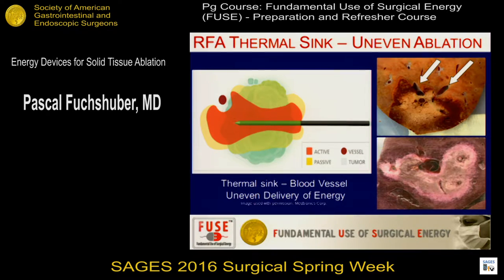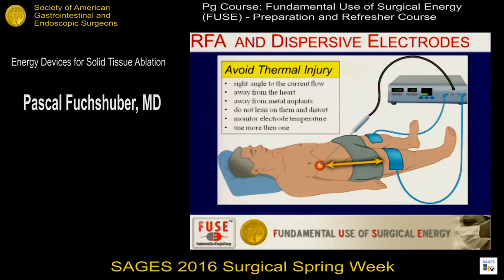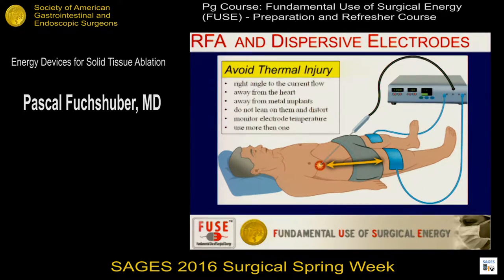The effect depends on what tissue you use it in and the water content of that tissue. High amounts of energy are used — up to 250 watts — so dispersive electrodes are at maximum capacity. If you change the anatomic layout of these electrodes, for example by leaning on them with your elbow, you can cause burns because energy focuses where contact is made. You also have to be very aware of electrode placement relative to the active site, and hip replacements can cause real problems.